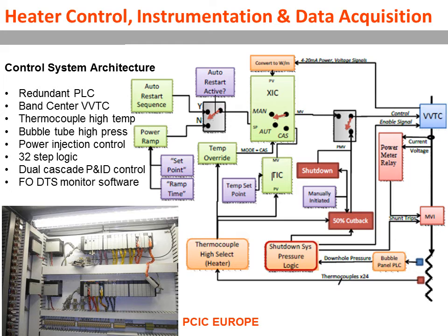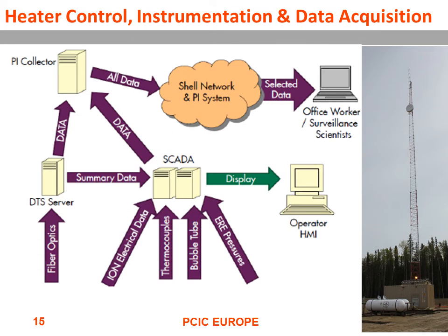This all worked very well except for the fact that the DTS through cycling failed early in the experiment in the pilot, but it still gave us information on the initial heat up. It's very hard to find DTS systems that will operate at 650 degrees C. They operate once, but then they usually fail on the cool down.